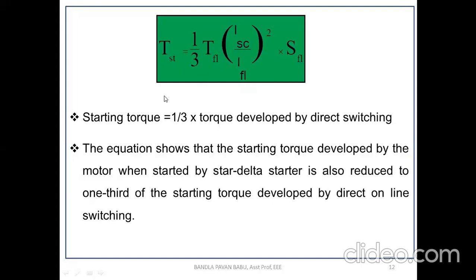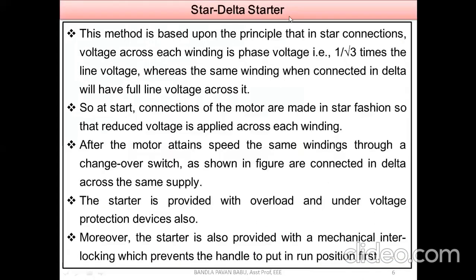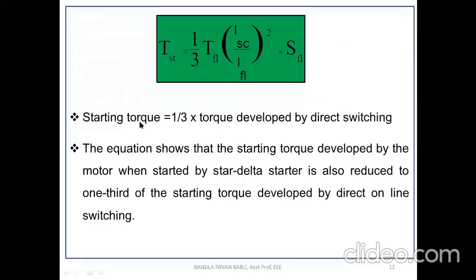So from this torque equation, what are we going to conclude? The starting torque in this method, that is the star delta starter, is equal to 1 by 3 of the torque developed by direct switching. Instead of directly switching the machine, which is not encouraged because there may be an increase of short circuit current, if you use this method, we can limit the torque to 1 by 3 times the torque developed by direct switching. So this equation shows that the starting torque developed by the motor when started by a star delta starter is reduced to 1/3 of the starting torque developed by DOL switching. That is one more advantage of using this method.